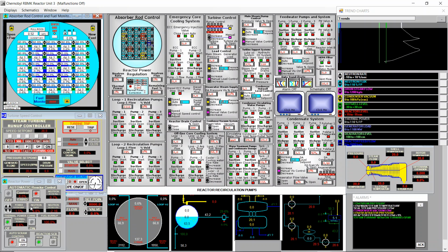Okay, neutron flux is at 1%. I will reduce now the power set point to 1 to see if it engages the automatic control. Increase to 1.5, pull rods. Hold. And I think now it's engaged. Do you see this sharp decrease here? So now I can already increase power just using the set point. This is very handy.